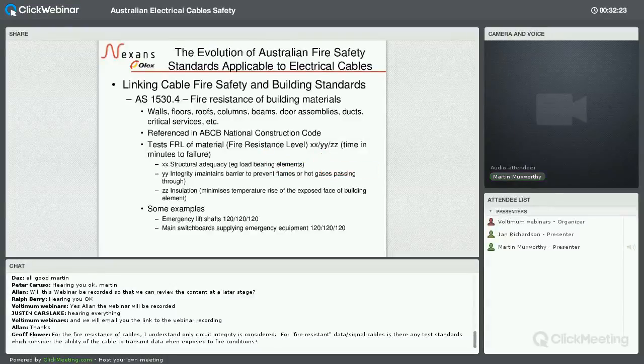XX, for example, relates to the structural adequacy of the load-bearing element. YY relates to the integrity of the building material. So, in the case of maintaining a barrier, for example, to prevent flames or hot gases passing through, it's a bit like preventing propagation of fire, if you like. And then ZZ is the ability of a material to insulate, so it minimises temperature rise of the exposed surface of a building element, insulating one side of a building element from the other. And I guess the obvious thing would be fire doors in buildings, for example. Some common examples.